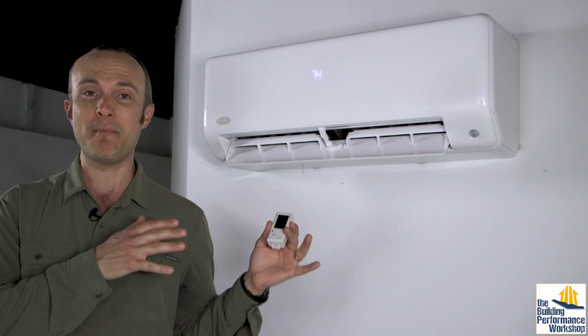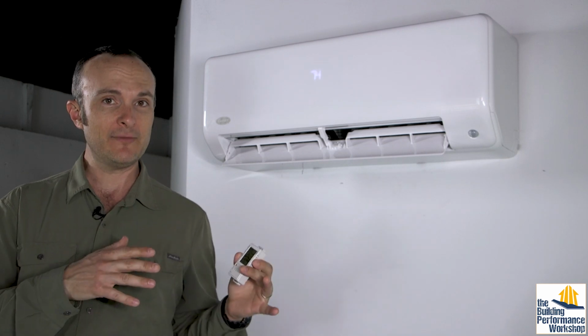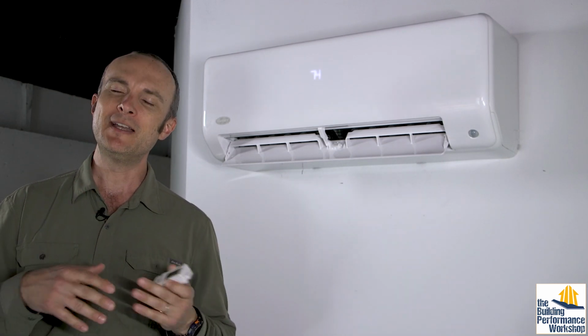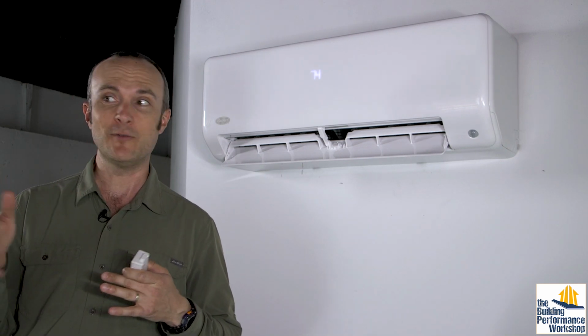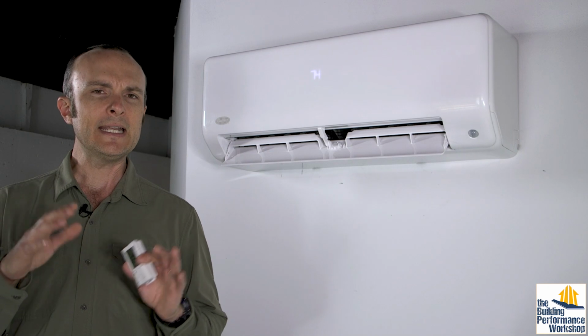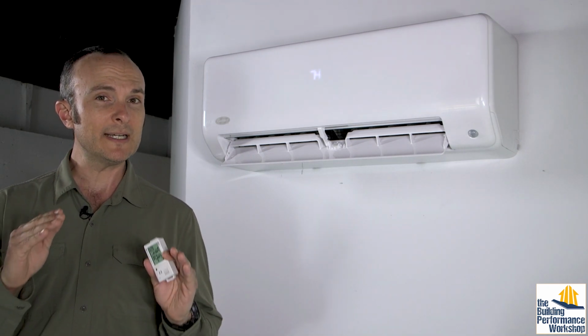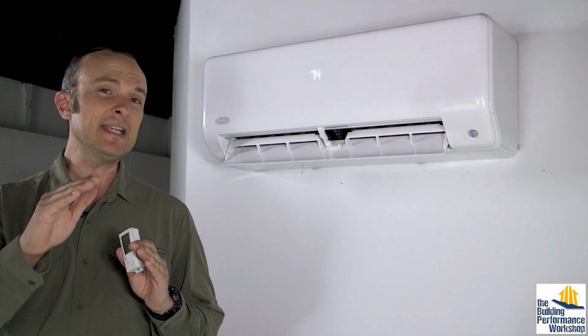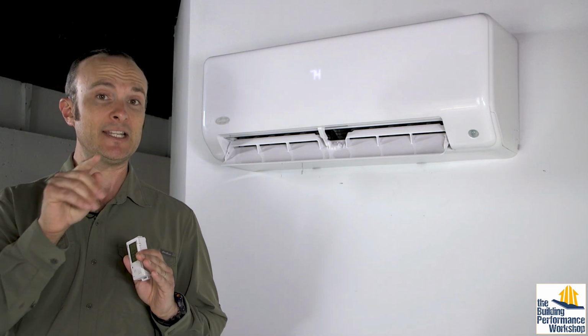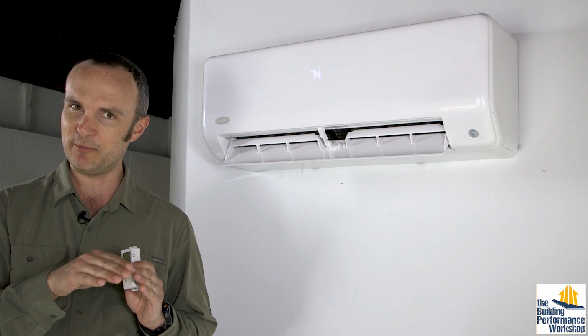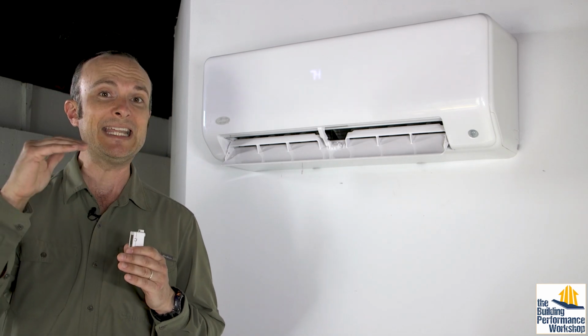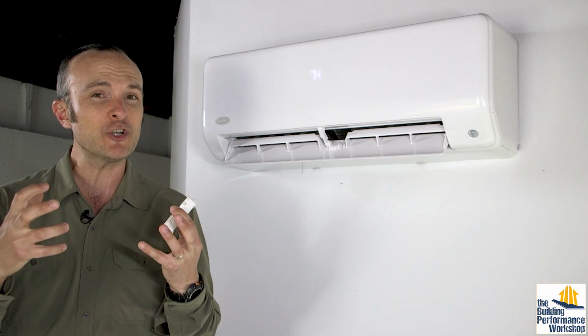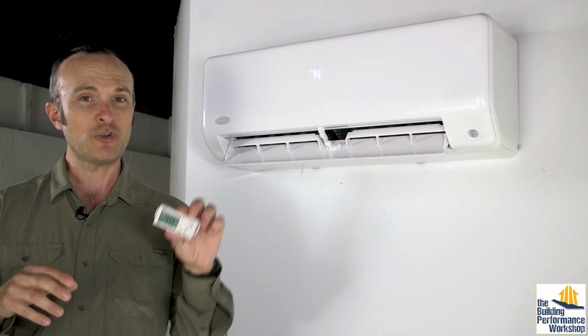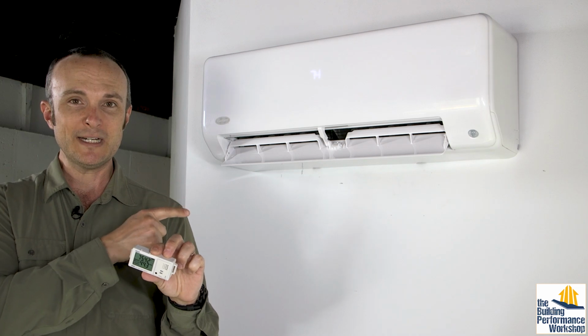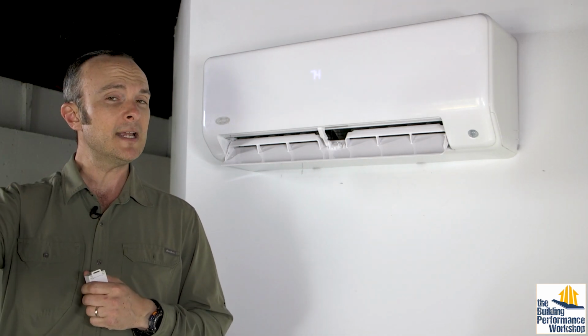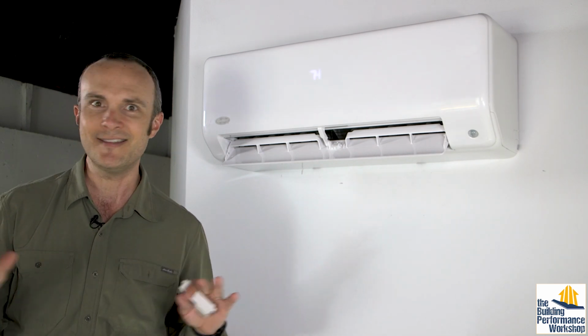It was pretty impressive to have that much cooling and drying coming out of one machine, and that's always nice to see when you get these started up, so that you know that they can perform on the hottest day of the year, which 91 is not as bad as it could get. And in case you're unclear about how important that relative humidity sensor is, when you're at your peak temperature, wherever you live, it's likely not as humid as it will be at a slightly lower temperature, like in the 80s. That's when you get really intense absolute humidity. That's when there's the most actual water in the air. So being able to track the humidity as this machine works is really important for both the peak temperature days and for the peak humidity days, which are not the same day.